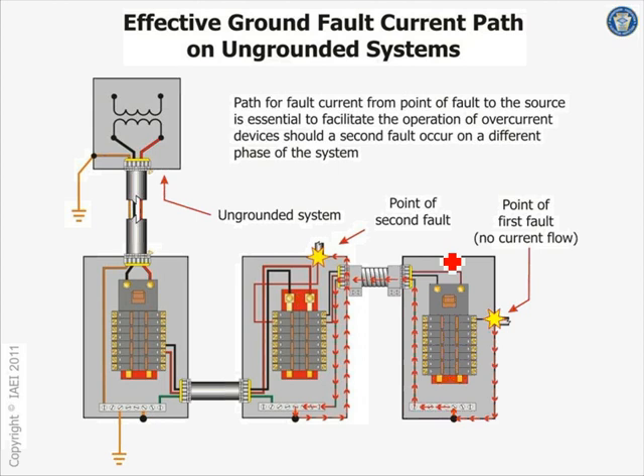So imagine an ungrounded system. The advantage of it is you eliminated interrupting your power system for 85% of your faults. Look how powerful that concept is. You have an assembly line, and remember, ground fault is 85% of your faults. Faults meaning short circuits and ground faults. 85% of your faults in your building are ground faults. If you have an ungrounded system or impedance grounded system, you have just eliminated 85%.